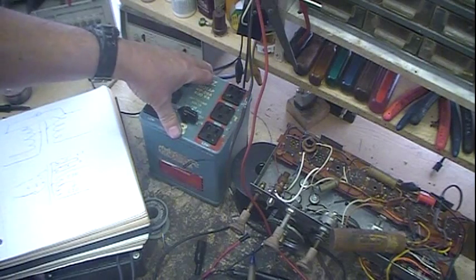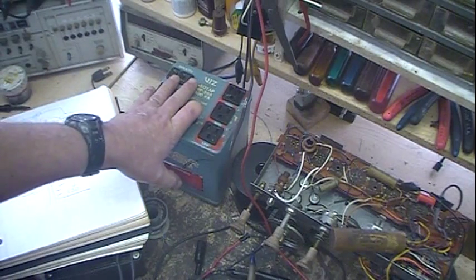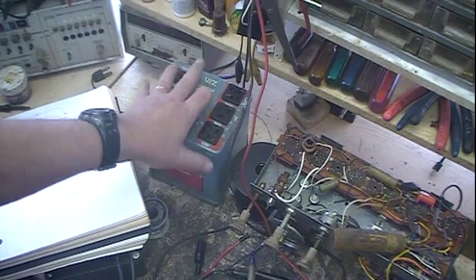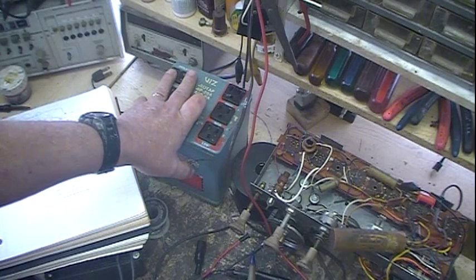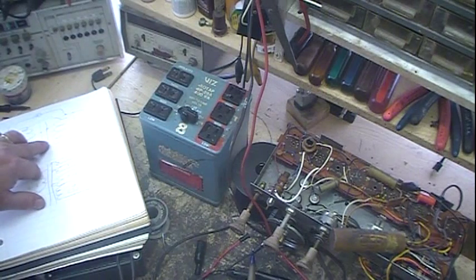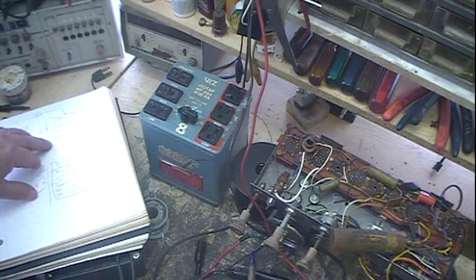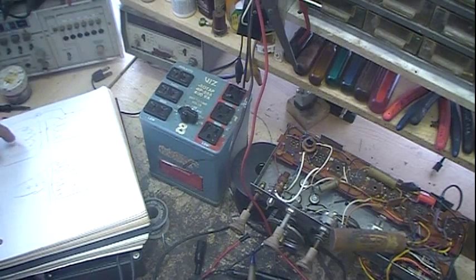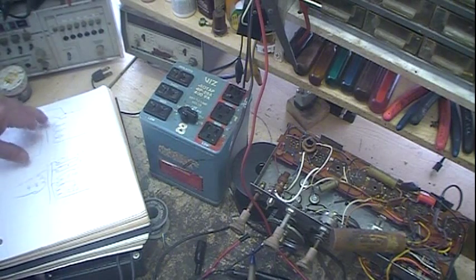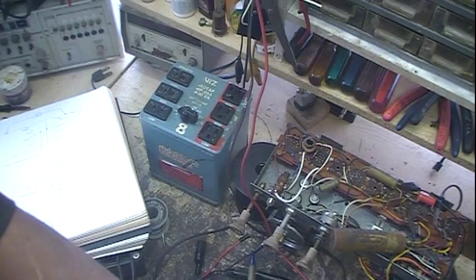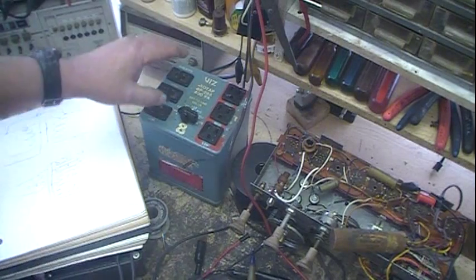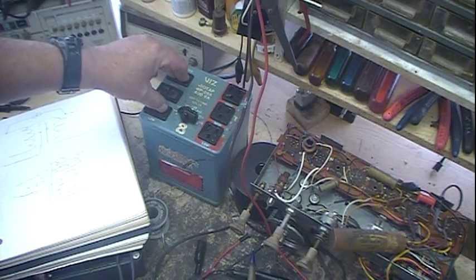The only real good test is an ohm meter, and to check for anything. Use the ohm meter, don't use the continuity tester, because if there's a short, and wherever you're hooking onto is in such a way somewhere in the midpoints of the windings, there could be enough resistance that the continuity tester won't pick it up. So don't do that.